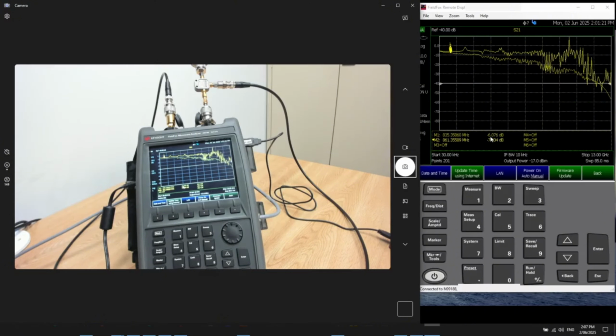So I got this question from someone asking that if in vector network analyzer mode, the calibrations can remove those errors, wouldn't it be applicable for cables also? So for example, if I'm using a very bad cable and after I run the calibration, wouldn't it calculate out all the errors contributed by the cables and still make my reading correct? I'm going to show you why it's not. Hopefully this will help you understand the beauty of the RF world.